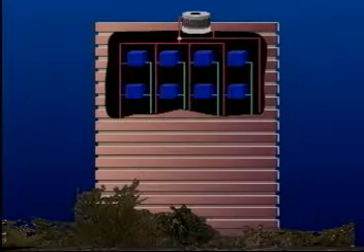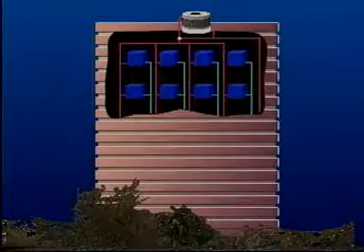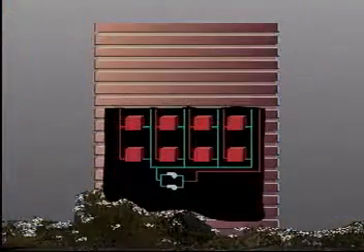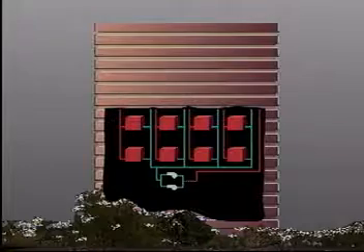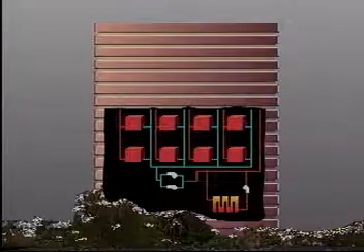The entire system is operating with an absolute minimum of energy. In summer, with the majority of units on cooling, the cooling tower evaporates excess heat to the atmosphere. During the winter, only when the temperature of the condensing water falls below 60 degrees is it necessary to add heat to the system.